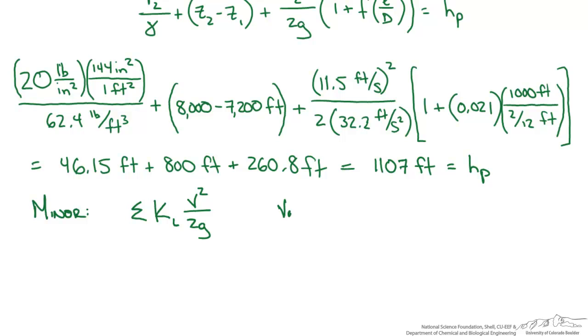Our loss coefficient for our valve, assuming it's fully opened, would be 0.05. Our two 90-degree bends each have a loss somewhere between 0.2 and 1.5 depending on the type. Let's assume somewhere in the middle, a KL ratio of 1, so two of these would equal a KL of 2. So our minor losses due to the valve and bends would be 2.05 times our kinetic variable. You can see this comes out to a very small number with respect to major losses.